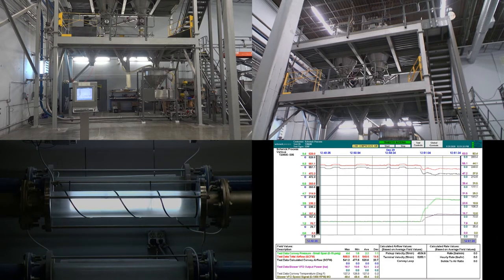Here we see plastic pellets being conveyed with normal design speeds on the blower across the typical distance. The lowest velocity in the system is 3,800 feet per minute. The blower is running around 50 hertz, and the energy to drive the blower is around 16 kilowatts.